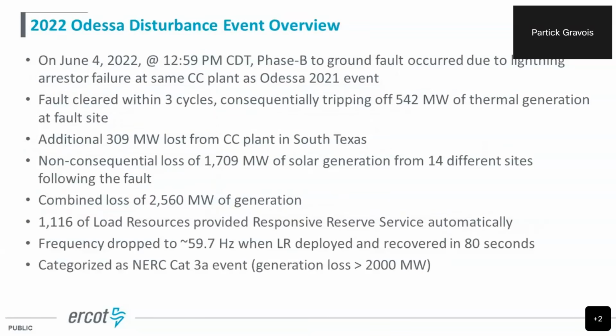All right, so let's move over to the 2022 event in June. That was around 1 p.m. Another single line to ground fault occurred at the same substation due to a lightning arrestor failure right near the Odessa area. Fault again cleared within 3 cycles, consequentially tripping off 542 megawatts of thermal generation at that site, at that one combined cycle plant.